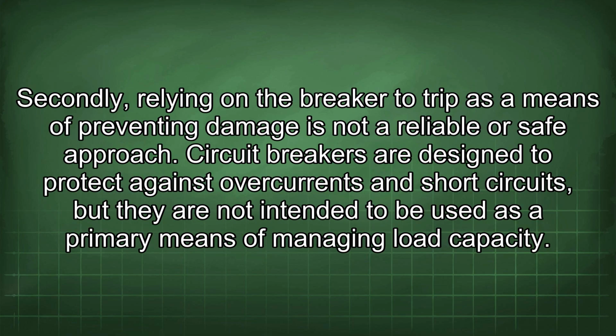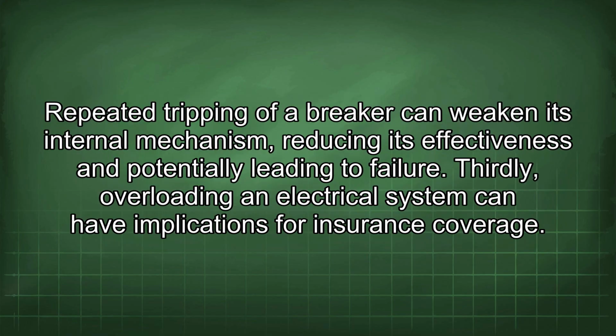Secondly, relying on the breaker to trip as a means of preventing damage is not a reliable or safe approach. Circuit breakers are designed to protect against overcurrents and short circuits, but they are not intended to be used as a primary means of managing load capacity. Repeated tripping of a breaker can weaken its internal mechanism, reducing its effectiveness and potentially leading to failure.